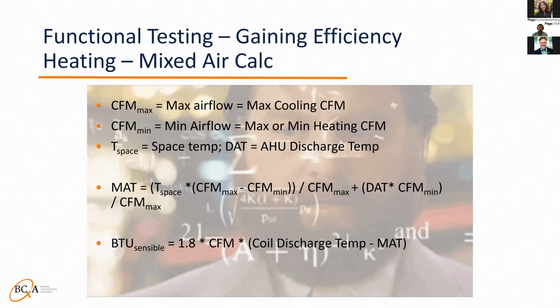Again, these are rough calcs to check coil performance for issues. And sometimes you don't even have to do the calc, because you can tell if all discharge temperatures are between 85 and 90 degrees, and if one is at 65 degrees, there is a problem. But I like to get a ballpark value to help me with this step.